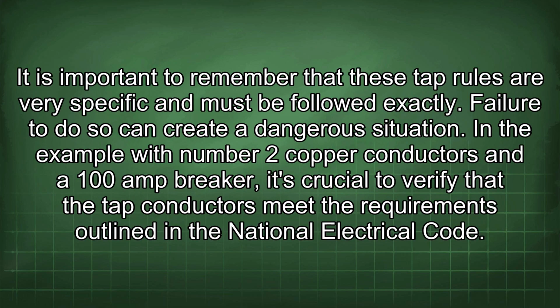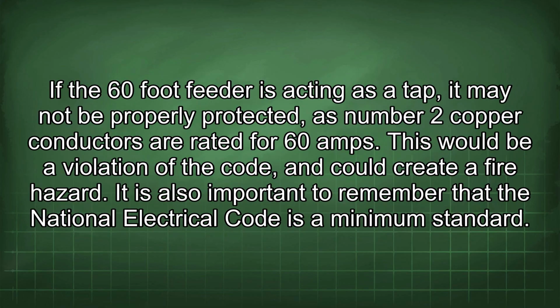It is important to remember that these tap rules are very specific and must be followed exactly. Failure to do so can create a dangerous situation. In the example with number 2 copper conductors and a 100 amp breaker, it is crucial to verify that the tap conductors meet the requirements outlined in the National Electrical Code. If the 60-foot feeder is acting as a tap, it may not be properly protected, as number 2 copper conductors are rated for 60 amps. This would be a violation of the code and could create a fire hazard.